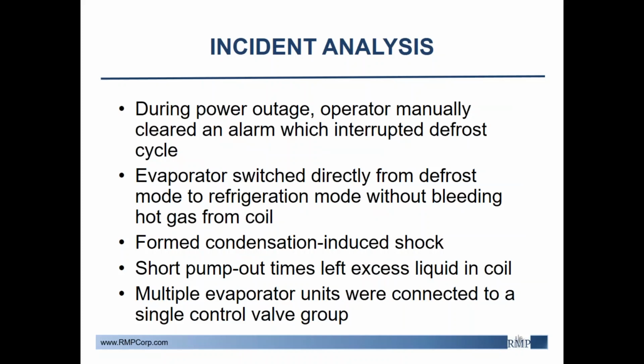So I don't imagine that's that common. This was an unusual circumstance because they had a power outage and it happened during the defrost cycle. So I can't imagine that that happens too often. As far as the evaporators all being connected, that was kind of an issue because you essentially have all of these evaporators connected to one valve system. So if something goes wrong, it's a lot easier for them to overpressure since there's so much ammonia going through this one valve system.